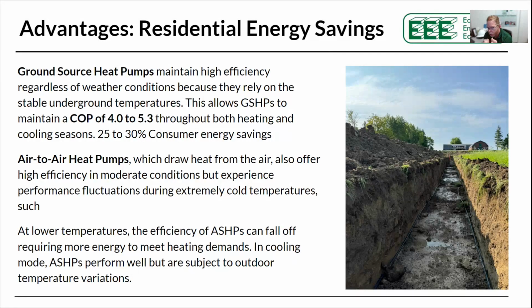There's no question a ground source heat pump is the most efficient solution, whether it's air to air or other, but you don't want to be laser focused on one thing. If you only look at the fact that, okay, I'm going to save let's say 25 to 30%, a number I've arbitrarily come up with based off ARI data, that's one part of the discussion. The other part is the fact that the equipment is going to last 2 to 3 times longer than a traditional heating and cooling system.